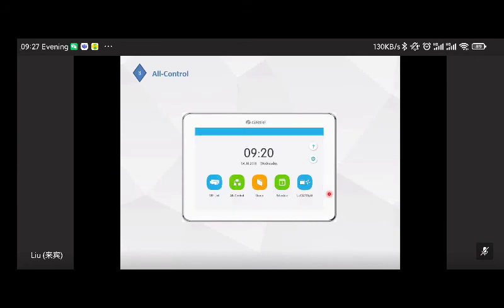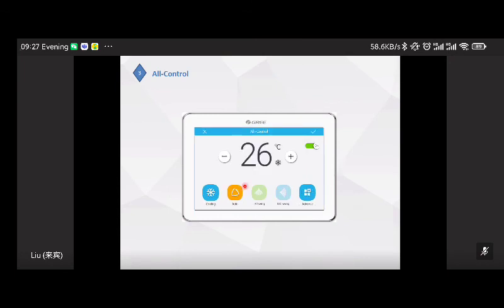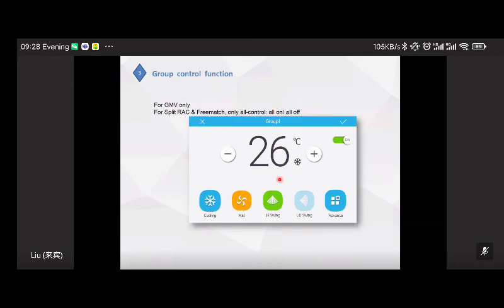And next one, you can see here, all control. If you press here, you can control all of the units connected with this central controller. All of the units. You can just change the setting here to change them all at the same time. So this is very good for a very big project to change all of the Indoor unit settings with just one operation. However, for split and free match, for the all control, only on off. Only on off.